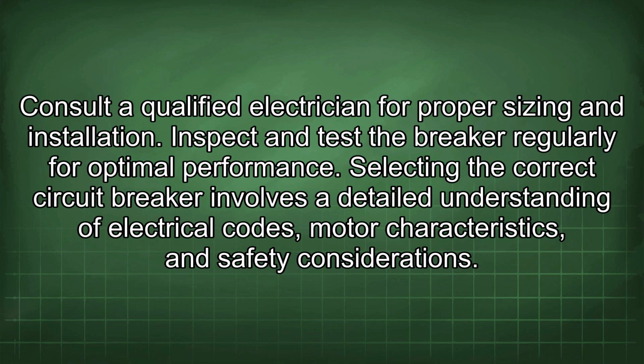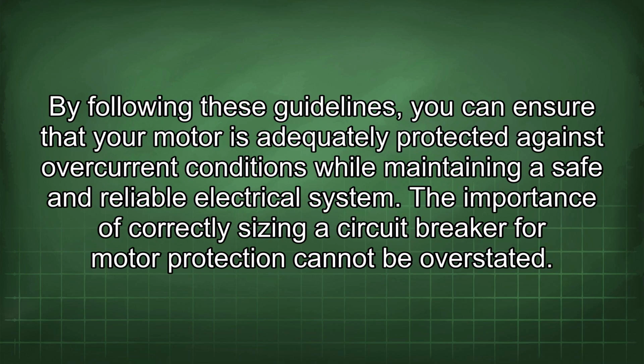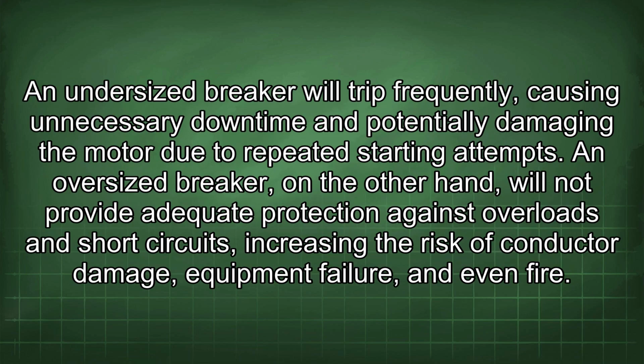Selecting the correct circuit breaker involves a detailed understanding of electrical codes, motor characteristics, and safety considerations. By following these guidelines, you can ensure that your motor is adequately protected against overcurrent conditions while maintaining a safe and reliable electrical system. The importance of correctly sizing a circuit breaker for motor protection cannot be overstated. An undersized breaker will trip frequently, causing unnecessary downtime and potentially damaging the motor due to repeated starting attempts. An oversized breaker, on the other hand, will not provide adequate protection against overloads and short circuits, increasing the risk of conductor damage, equipment failure, and even fire.